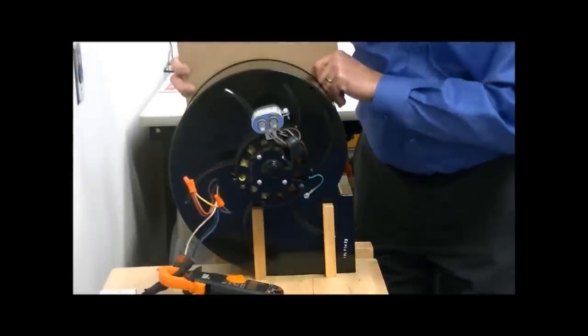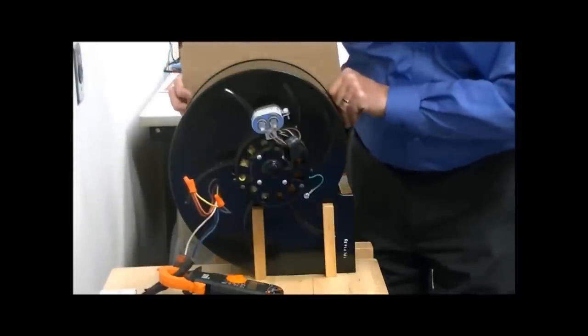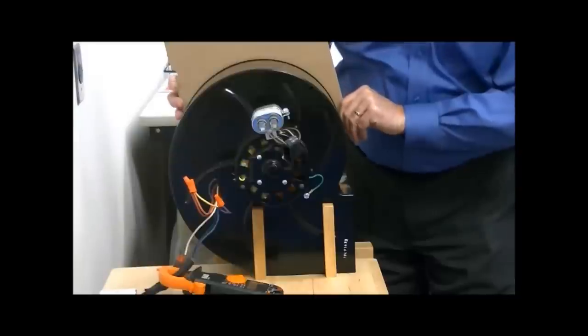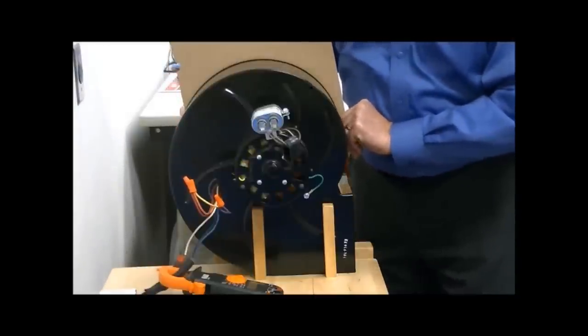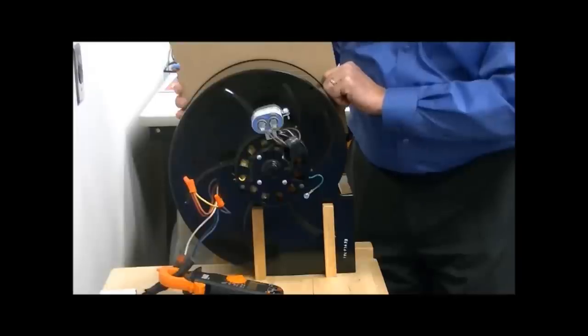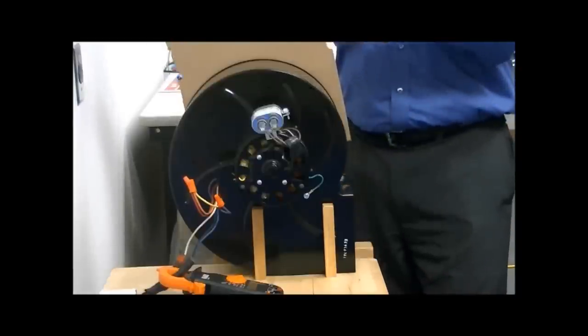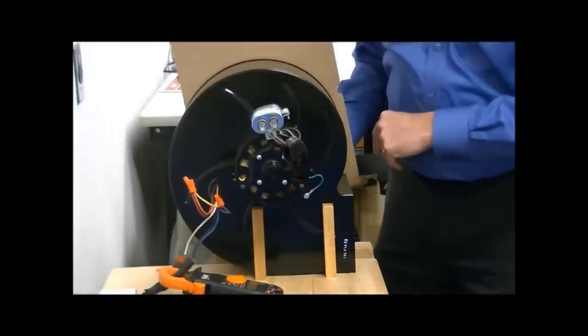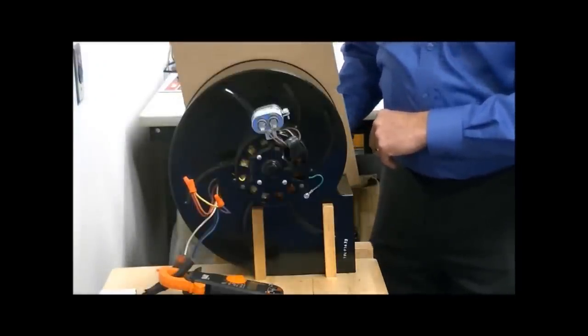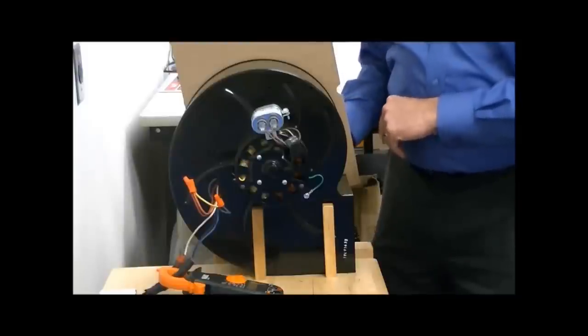As I add restriction, the amps drop. With half of the inlet blocked, the motor operates at 2.5 amps. With the entire inlet blocked, the motor operates at 2.3 amps.